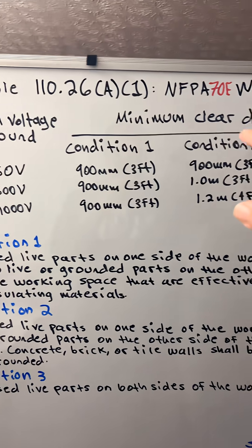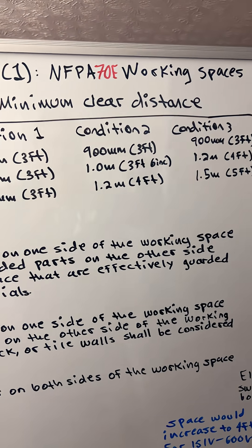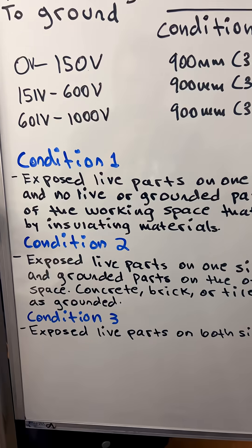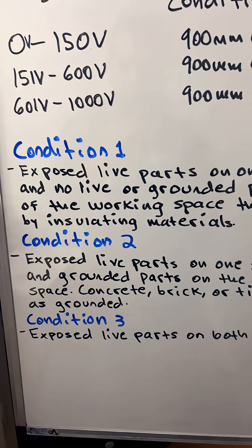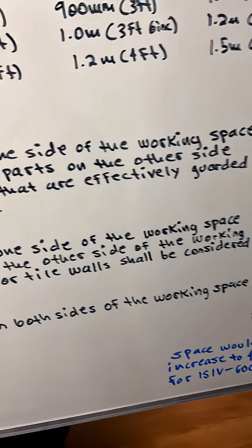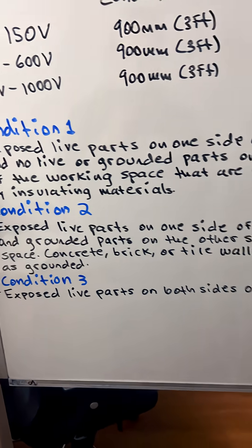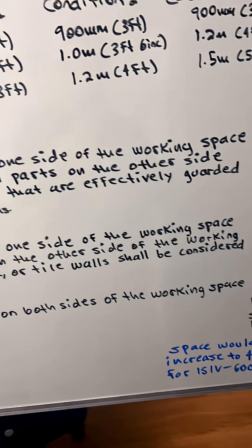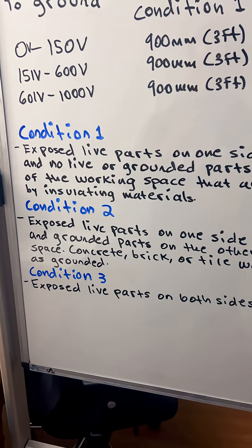We have the minimum clear distance for condition 1, condition 2, and condition 3. Condition 1 is exposed live parts on one side of the working space, and no live or grounded parts on the other side of the working space that are effectively guarded by insulated materials.